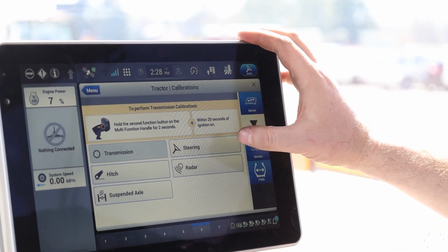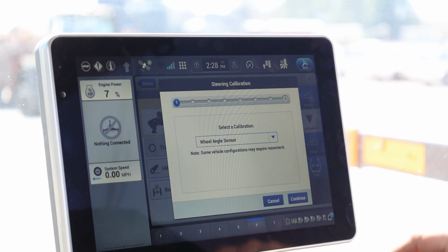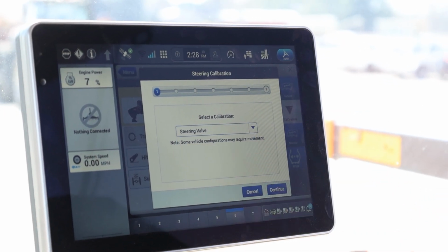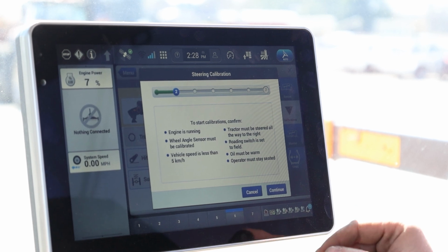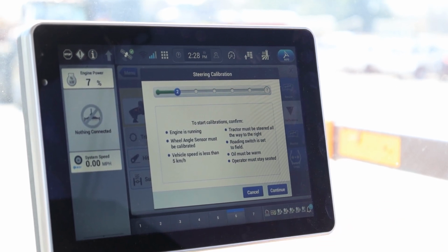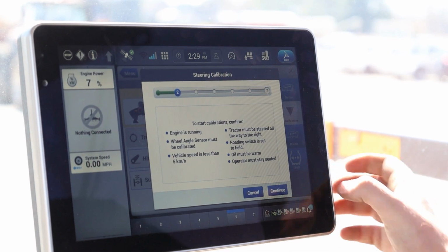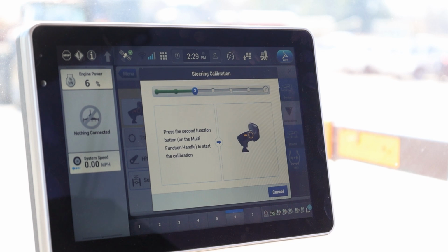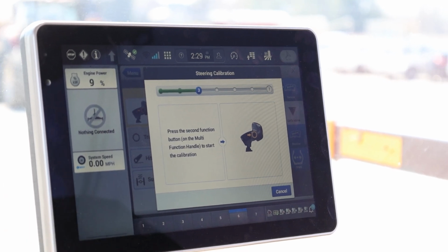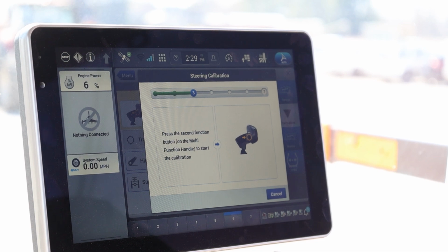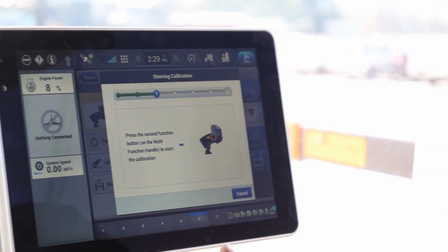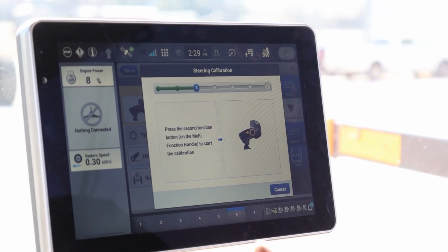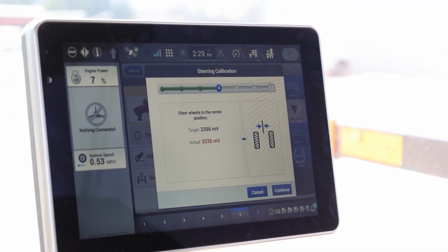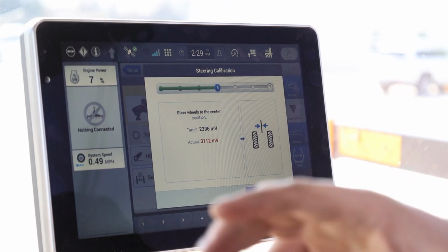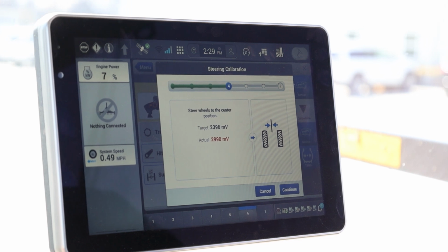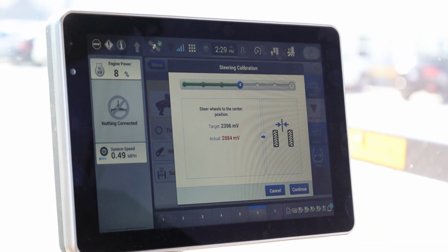Once the wheel angle sensor calibration has been completed, we can click on steering again and select steering valve. For this test, the hydraulic fluid needs to be at the operating temp of the tractor. To begin this test, we do need to steer the wheels fully right and then press the button on the back of the multifunction handle. For this test, the tractor will move on its own. No steering will be required, and you do need a large area to do this test.